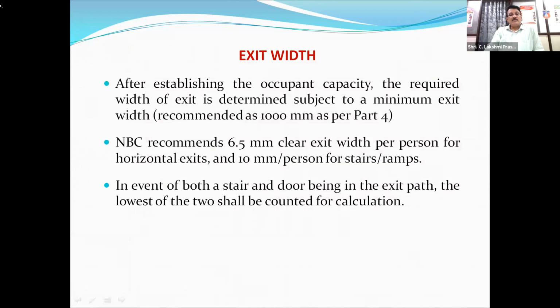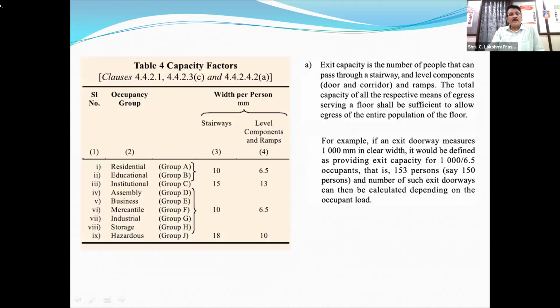Then this is 6.5 mm clear width per person for horizontal exits and 10 mm for staircases or ramps. See, horizontal exits are provided especially in hospitals and institutional buildings to facilitate various services from one block to the other, or to move patients with the help of stretchers in case of emergencies. Then the occupant load capacity factors, these are taken from the international codes. If you see all this, mostly for residential and educational, it is 10 mm per person. For institutional, it is 15 mm. And for assembly, business, mercantile, industrial, and storage, it is 10 mm per person. And for hazardous buildings, it is 18 mm per person.